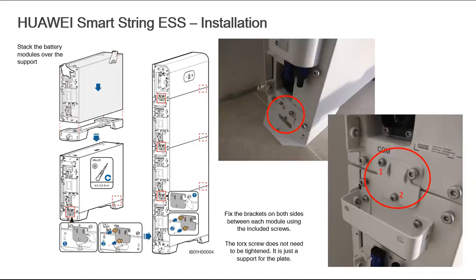If you don't do it, there is a risk that it can fall down if something happens to the battery. So always make sure to use the battery expansion plates on both sides of the battery, so that you can fix the battery to the floor stand and the two module stacks to each other. The screws are also provided inside the module battery box, so you can use them to tighten the battery expansion plates.